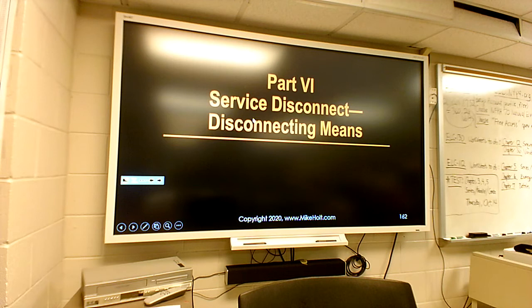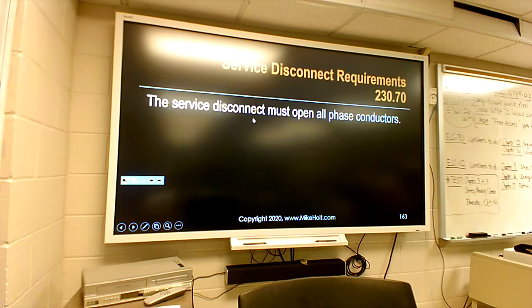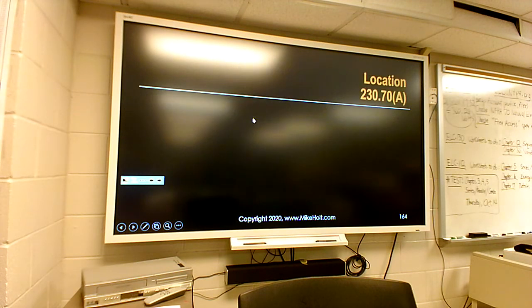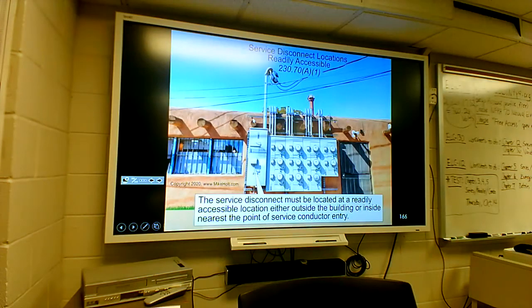Part 6, service disconnect. Disconnecting means the service disconnect must open all of your phase conductors, all of your hot wires. It must be readily accessible. So the disconnect must be located at a readily accessible location, either outside or inside, nearest the point of service conductor entry.